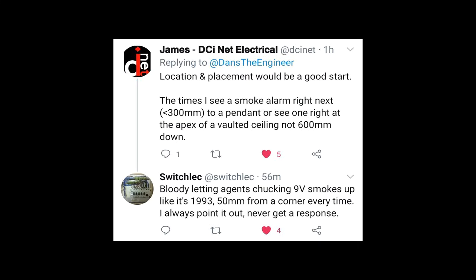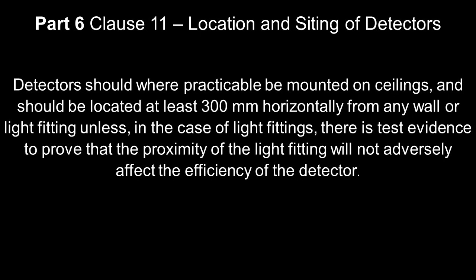So James on Twitter has said location and placement would be a good start. The times I see a smoke alarm right next to a pendant, less than 300mm away, or one right at the apex of a vaulted ceiling, not 600mm down. So, right, let's run through some of the basics of where you site them. Clause 11 in part 6 tells you exactly where you put detectors, the ins and the outs. So I'm just outlining some of the main points.